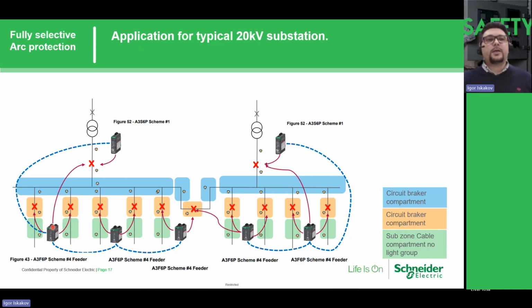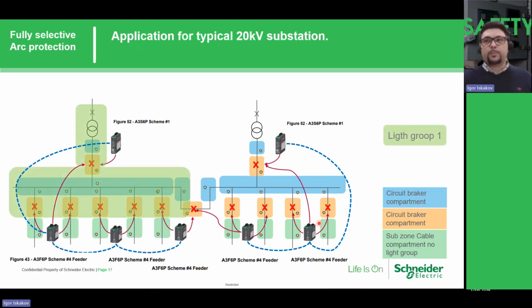And in this case, we have an additional tripping contact, which is 9 milliseconds slower, but we can secure the trip on the upper level of the switchgear, like circuit breaker protection. So we are able to also protect our incomer on both parts. By dividing this substation into left and right sides in groups, we are also able to protect our substation from the different parts.